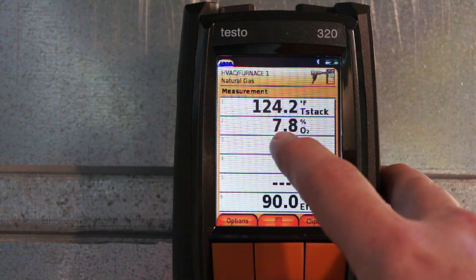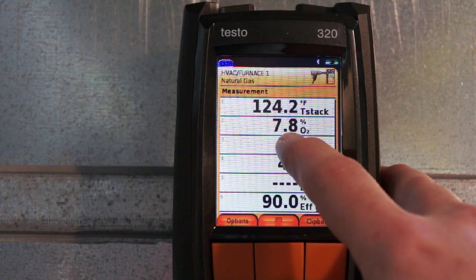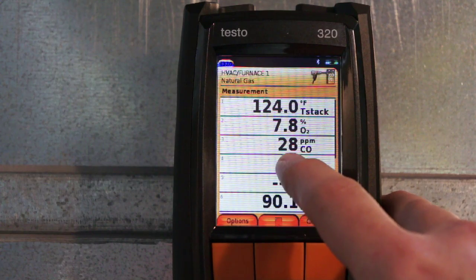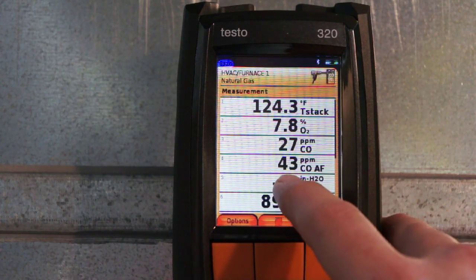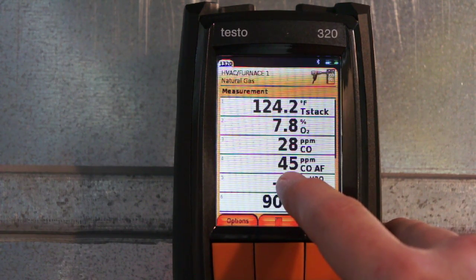Now, you can see I got 7.8% O2. Pretty typical for a 90 plus furnace. I want to see that somewhere between 5 and 7% oxygen. I'm at 28 parts per million CO. I'm at 43 parts per million CO air free.